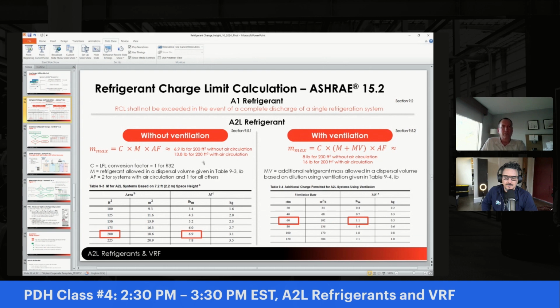And when there is ventilation, the equation is the same, but there is a refrigerant mass variable that's added in here. And again, this ventilation can be mechanical or it can be continuous or triggered by your refrigerant leak detection or whatnot.